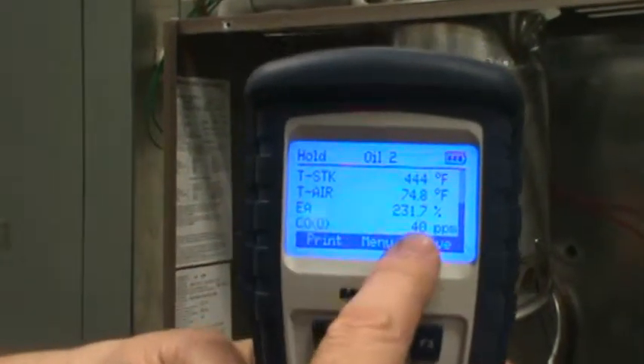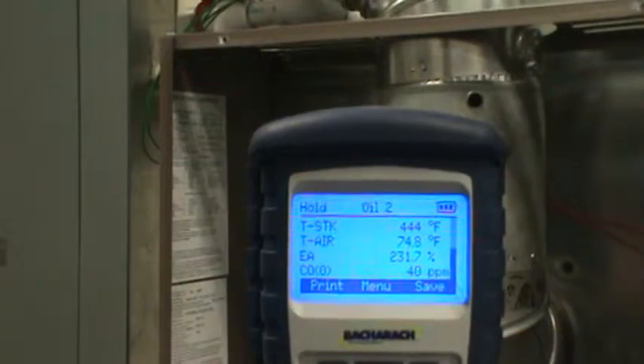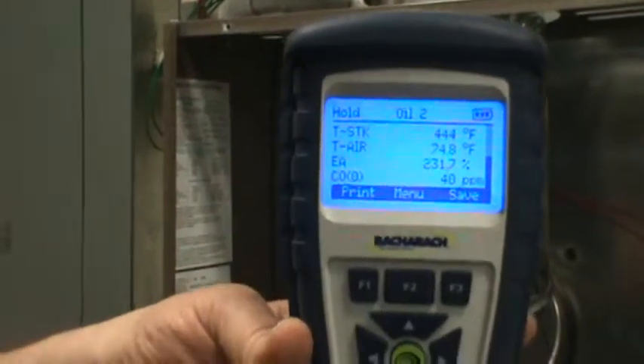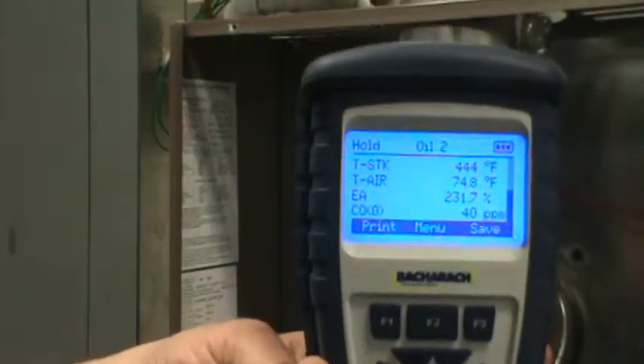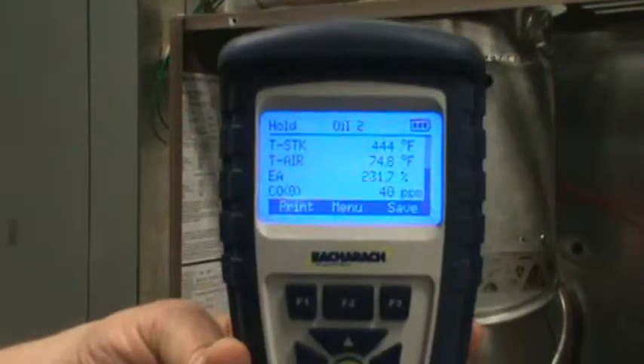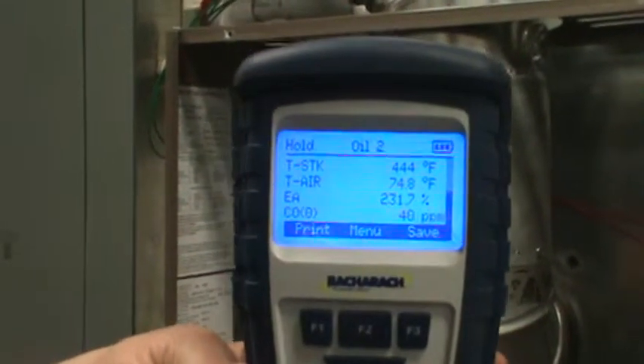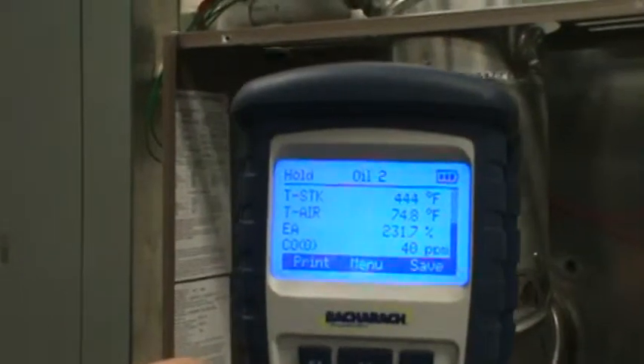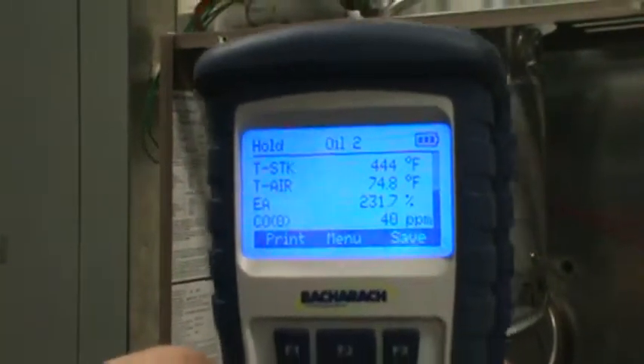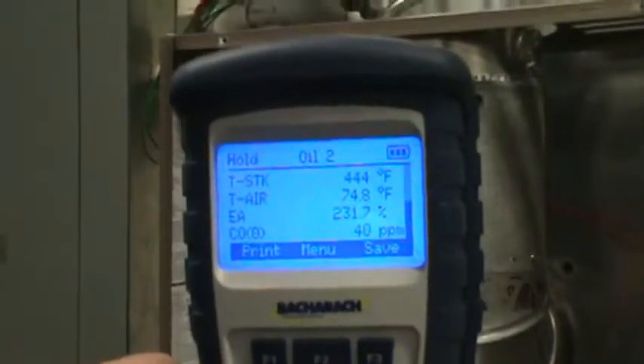The CO is telling me 40 parts per million. That's a good burn. So what that CO is saying, if you didn't have any excess air, what carbon monoxide will be put out by this system? So that's a good indicator of how well my burn is, how well the device is actually burning.